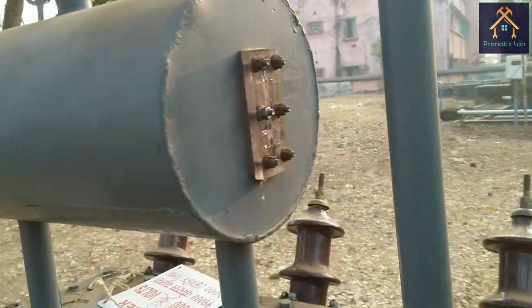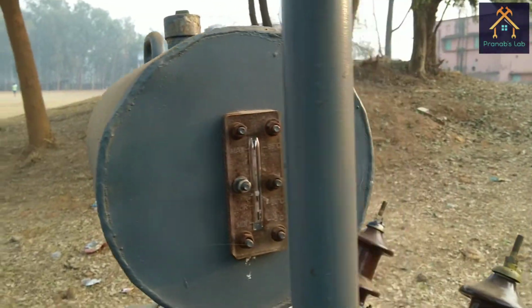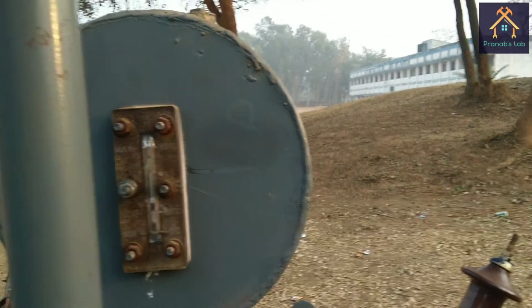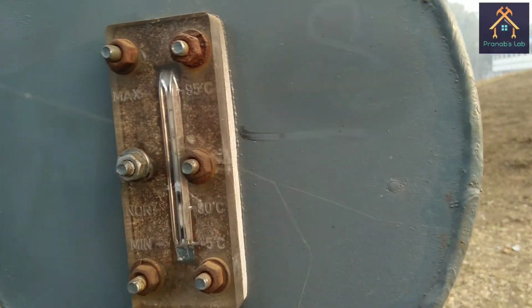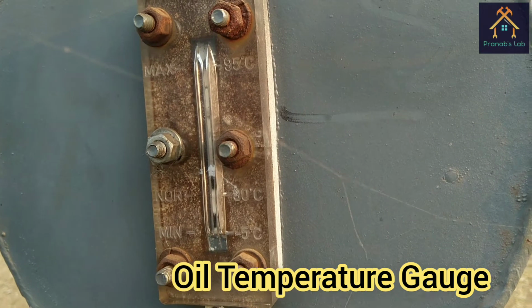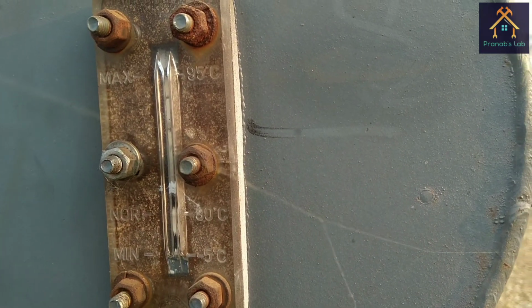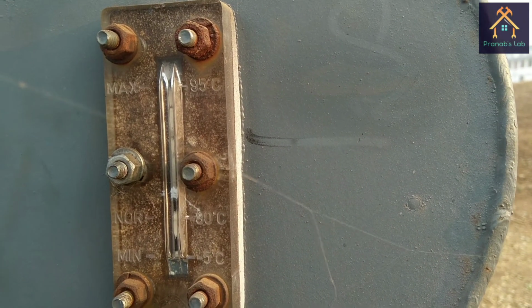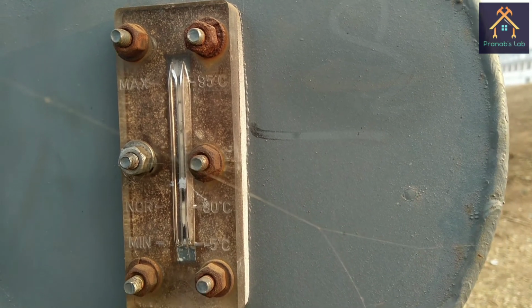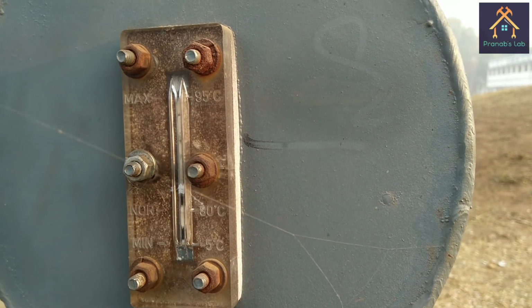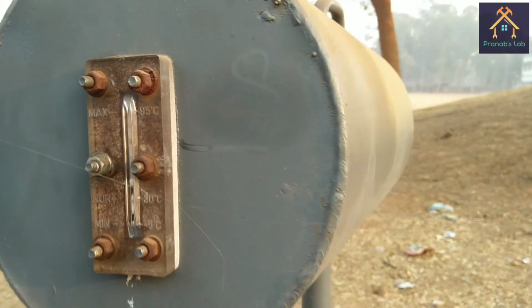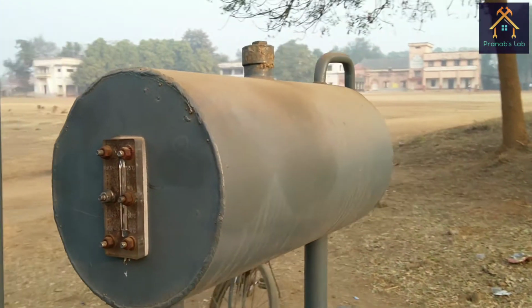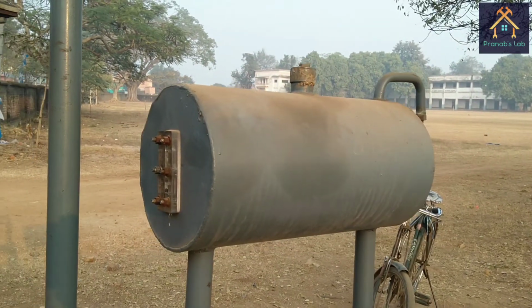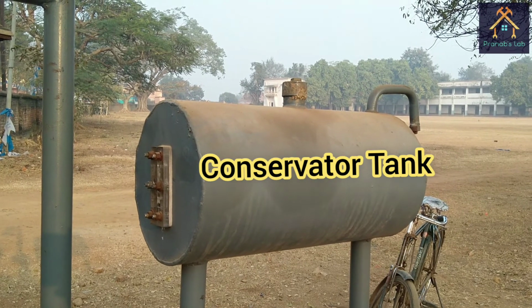So we can say this is a safety device. Now you can see this is the mercury filled temperature gauge or thermometer. -5 degrees Celsius minimum, normally 80 degrees Celsius and 95 degrees Celsius maximum temperature can be measured by the thermometer. Actually it measures the temperature of the transformer oil, and the gauge is placed on the conservator tank.